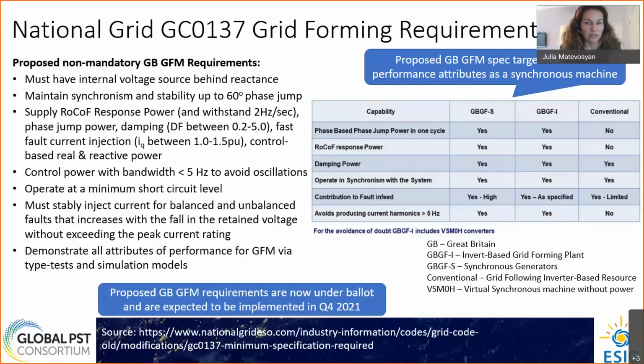And on the right-hand side, you can see a comparison between conventional grid following inverters, grid forming inverters, and grid forming synchronous generators providing these functions. And so you will see, if you look across the capabilities that are required, that basically in this specification, the target was to achieve the same or similar performance attributes that synchronous machines are providing today.